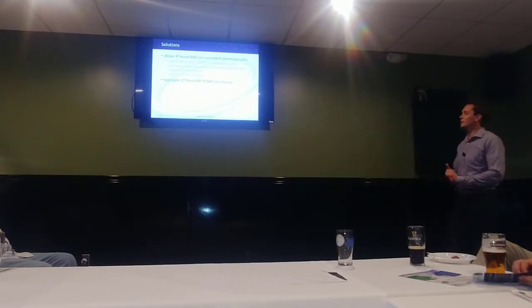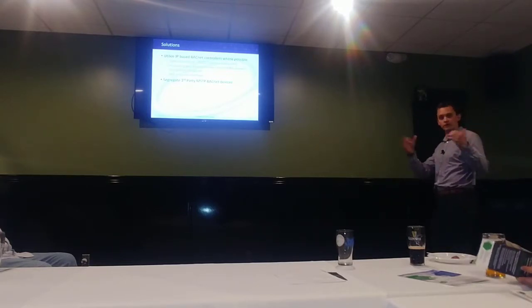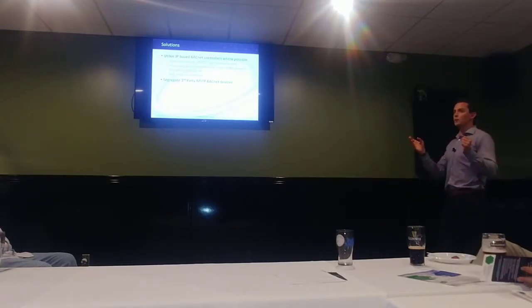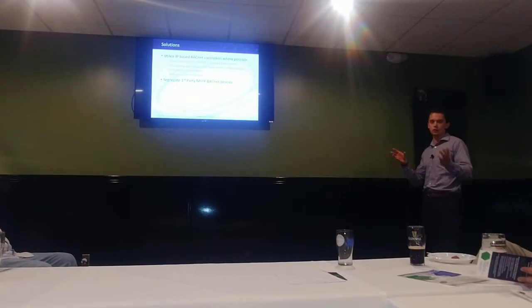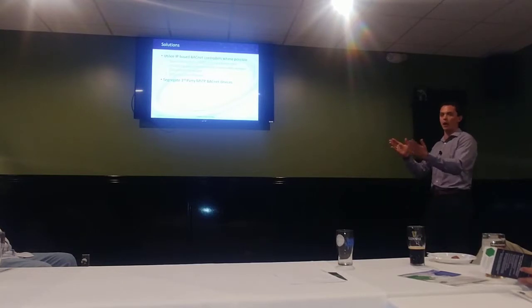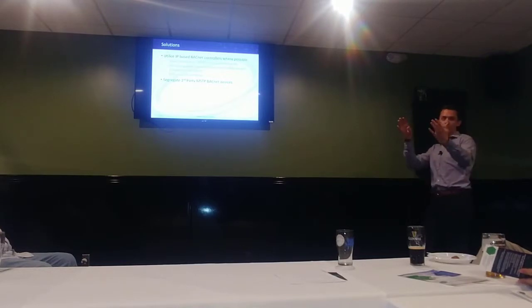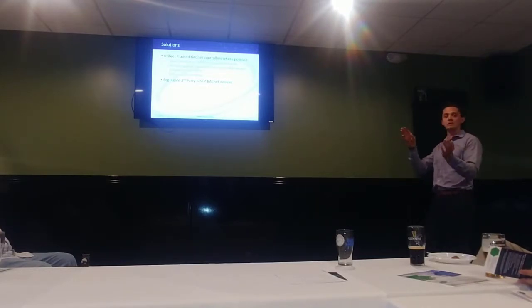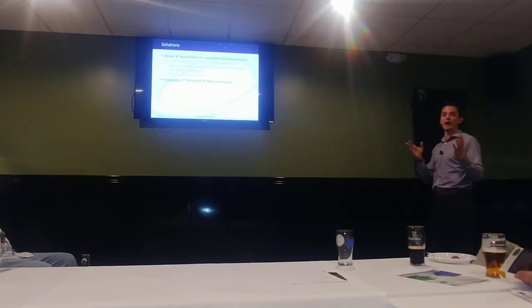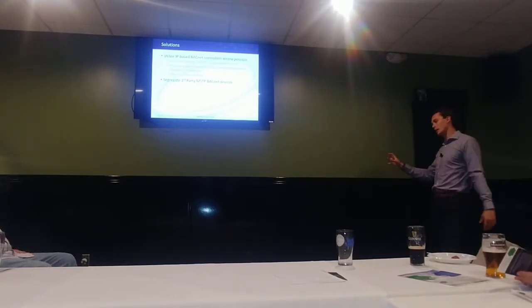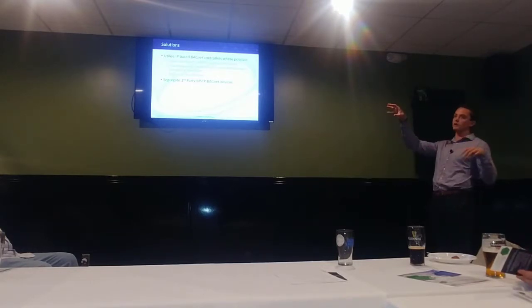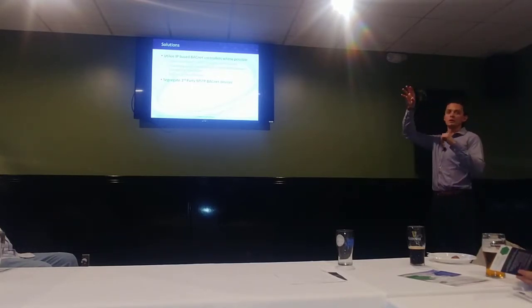Some of the things we had to keep in consideration is utilizing BACnet IP controllers where possible. I showed you that manufacturing suite example before. What we found is that trying to do conventional VAV control with all of those points created a huge bottleneck for us. Even with a powerful system level controller with a powerful processor, we still were getting a bottleneck up at the HMI side when we pulled up a floor plan, for instance. We pull up a floor plan of 10, 15 boxes, and we would get a huge delay in getting all that data from the VAV boxes through the system controller, up into the ProSoft cards, through the ControlLogix, all the way into the SCADA system.